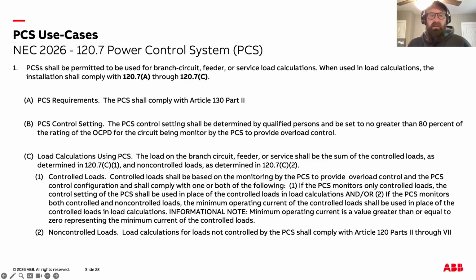NEC 120.7 is where the code formally recognizes the use of power control systems in branch circuit, feeder, and service load calculations. This section is dense, so it helps to break it down into its core ideas. To start, 120.7 requires that any PCS used for load calculations must comply with Article 130, Part 2, which we reviewed earlier. A key requirement is that the PCS control setting, the ampere limit the PCS enforces, must be established by a qualified person, and that settings cannot exceed 80% of the rating of the OCPD protecting the monitored circuit. This 80% cap ensures the PCS provides a reliable safety margin when it is being used to prevent overloads.